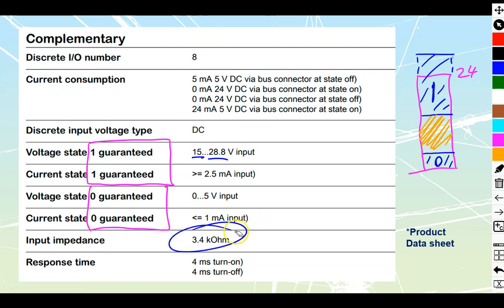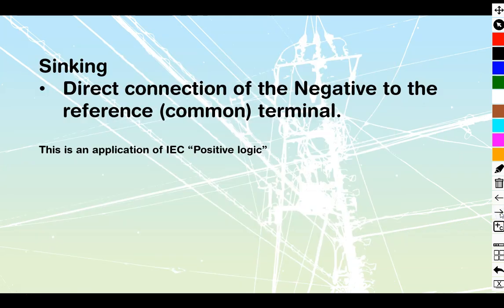Input impedance is going to be 3.4 kilo ohms. This is just going to limit the amount of current we have coming in there. And then response time is going to be in the milliseconds for turn on and turn off. We're going to be using a sinking input connection. Sinking always refers to a direct connection of the negative to the reference or to the common terminal. And the way that we're using this as sinking on input would be an application of IEC positive logic. There is a complete other video out of the 221 video set that deals with sinking and sourcing. It's about 20 minutes long. So if you don't understand them, watch through the whole thing. We go through sinking, sourcing, and then we also go through IEC positive logic and negative logic. Hopefully, it should be enough that you can get an understanding of that topic because it's critical. There is some danger using the IEC negative logic, not with the positive logic though.